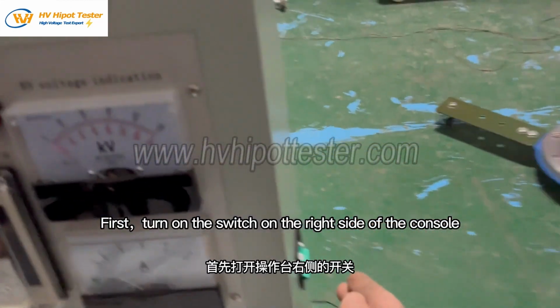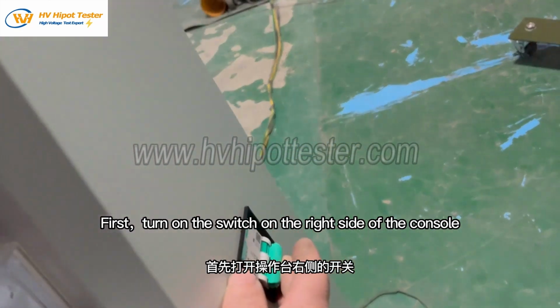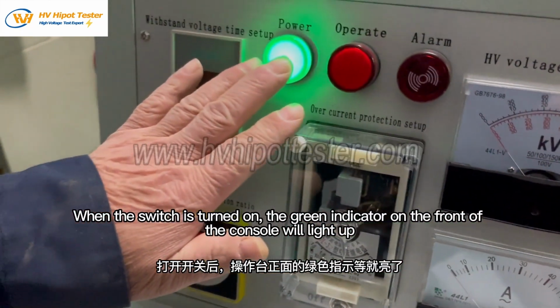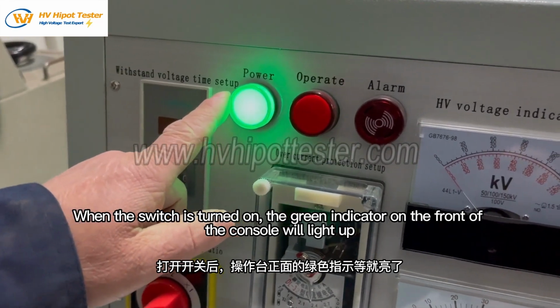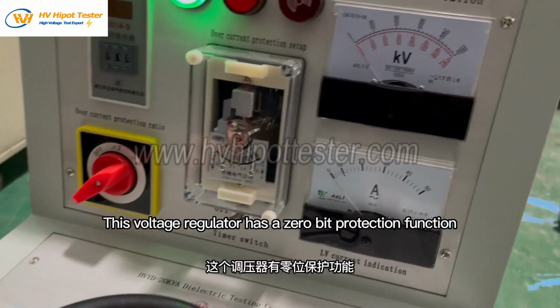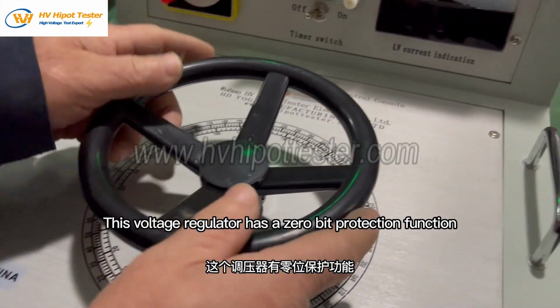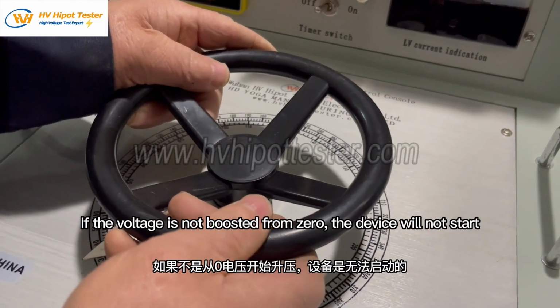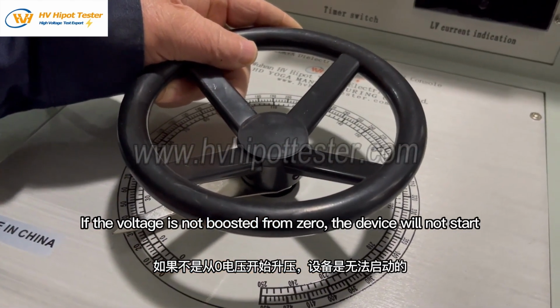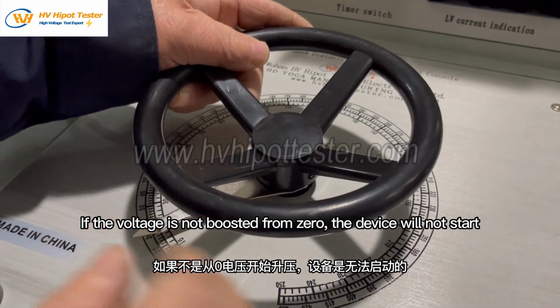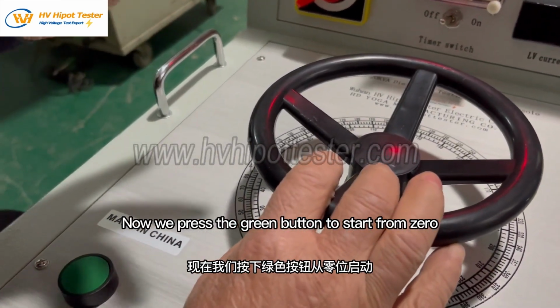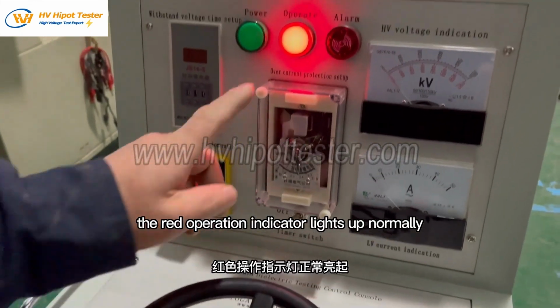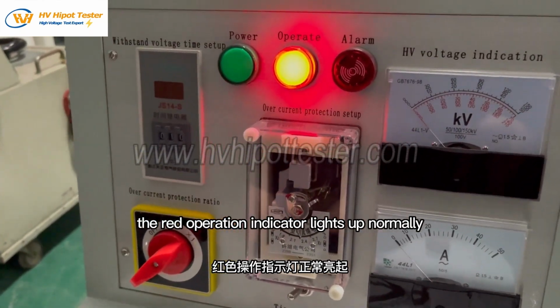First, turn on the switch on the right side of the console. When the switch is turned on, the green indicator on the front of the console will light up. This voltage regulator has a zero-position protection function. If the voltage is not boosted from 0, the device will not start. Now we press the green button to start from 0. The red operation indicator lights up normally.